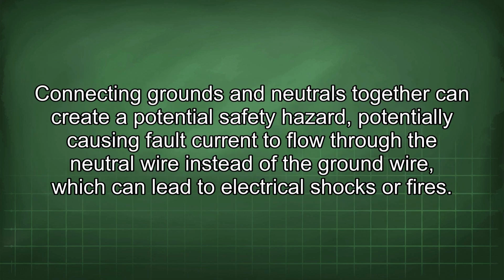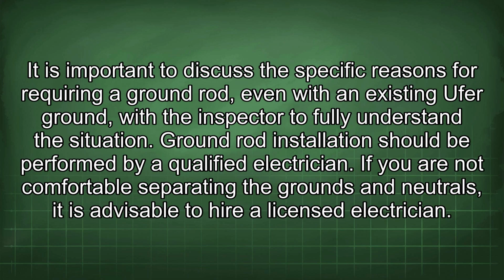Connecting grounds and neutrals together can create a potential safety hazard, potentially causing fault current to flow through the neutral wire instead of the ground wire, which can lead to electrical shocks or fires. It is important to discuss the specific reasons for requiring a ground rod, even with an existing Ufer ground, with the inspector to fully understand the situation. Ground rod installation should be performed by a qualified electrician. If you are not comfortable separating the grounds and neutrals, it is advisable to hire a licensed electrician.